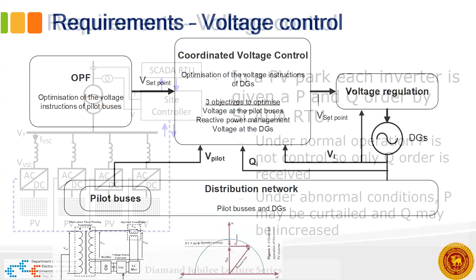More importantly, if you are going with a large distributed system like a mini grid, you need more coordinated control, because you cannot just control one inverter, you need to control these inverters. That's why we need smart meters to achieve that controllability. Once you have that controllability, you can tell each inverter what their set point should be. These are small computer programs that you can run on a small control center to decide how to control these inverters.